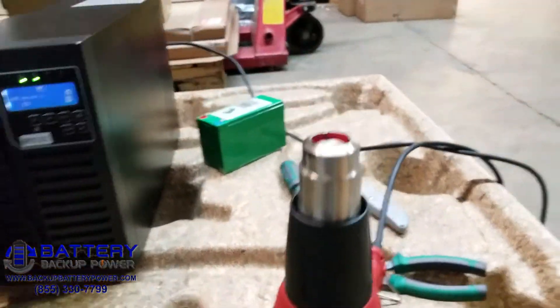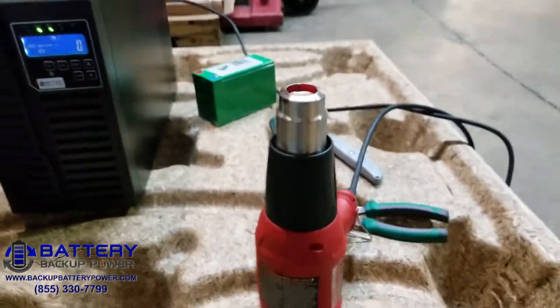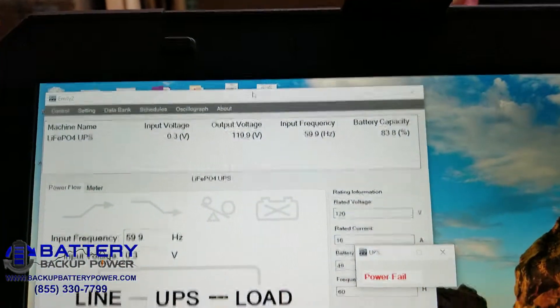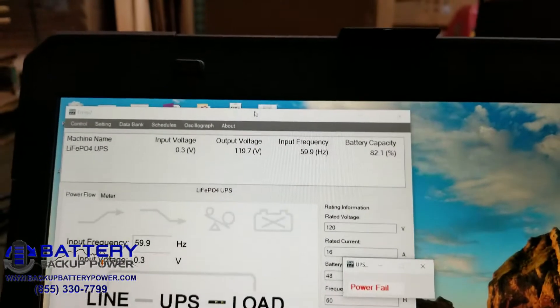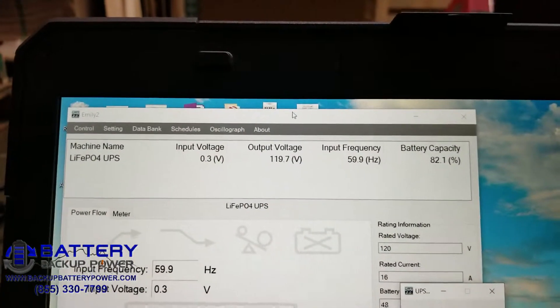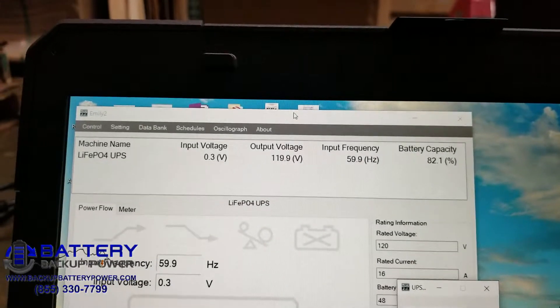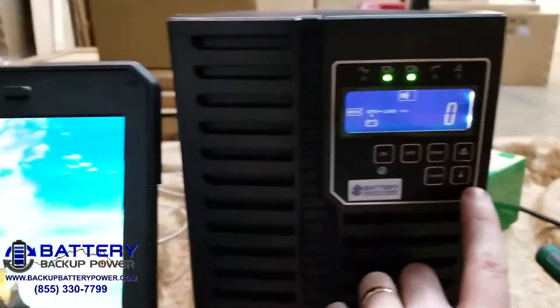You can hear the heat gun is still going. We can see that power has failed. The input voltage is zero, output voltage 119.7 on the lithium iron phosphate UPS.